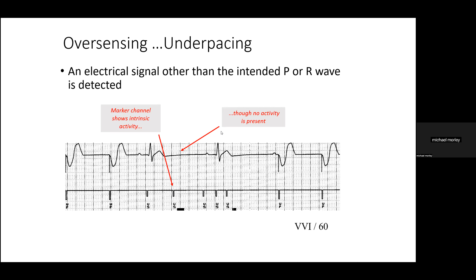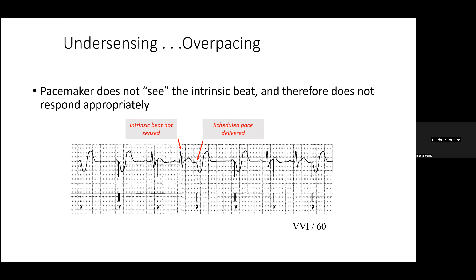And the converse of that is that undersensing leads to overpacing. And in this situation, we've got ventricular pacing spikes marching all the way through, some of which are capturing the ventricle. But we can see that there are some inappropriate pacing spikes because the device is not sensing the underlying intrinsic activity.